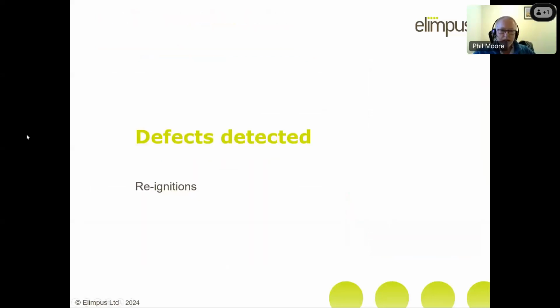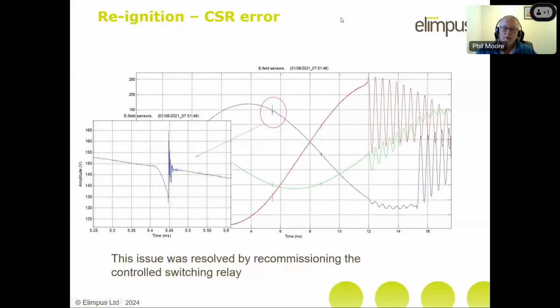So let me tell you another one. Let's talk a little bit about reignitions. This was a circuit breaker, an AIS circuit breaker again, and we were asked to go along and look at it. And when we looked at it closely, you can see on the blue, this is the blue phase electric field, you can see there's a little spike there. And if I just expand that, you can see what's happened here is that this has actually gone into the reactor transient, and then for maybe 50 microseconds or so, suddenly the arc has reignited there.